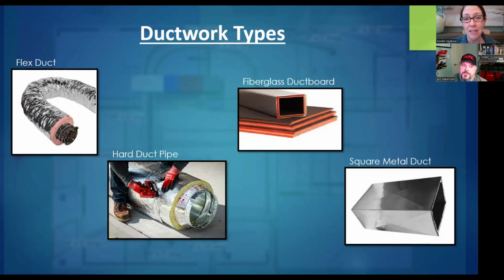Let me throw this out too — just because you have an all hard duct system doesn't mean it's right. Was it designed? Is it sized properly? Is it running super high static pressure? Do we have the airflow through it? Is it delivering air where it needs to be? You might walk up to a system that's all hard pipe, done beautifully, but if it's not doing what it's supposed to do, I still can't do anything with it.